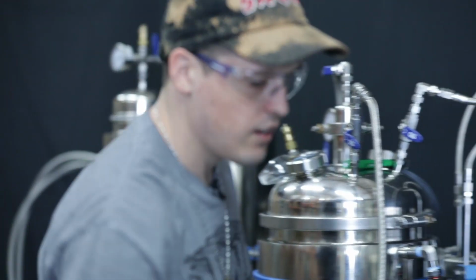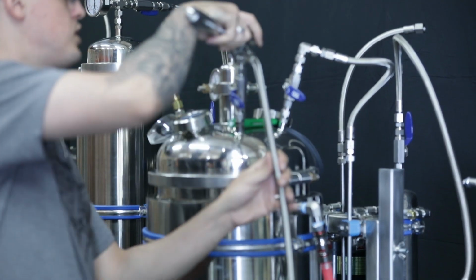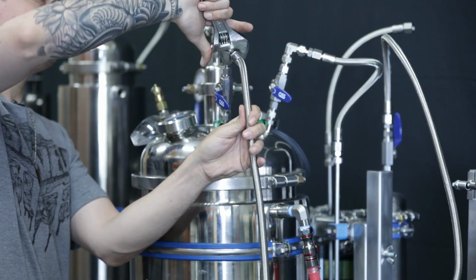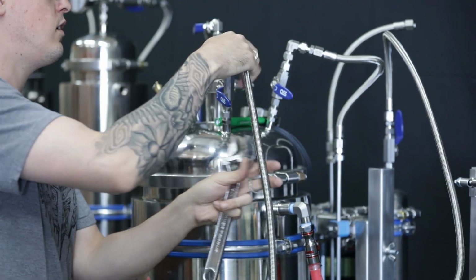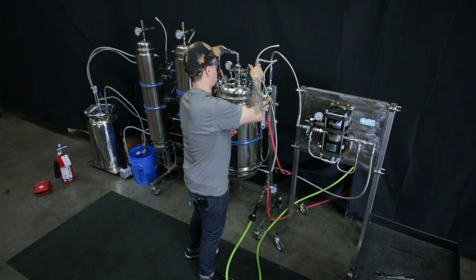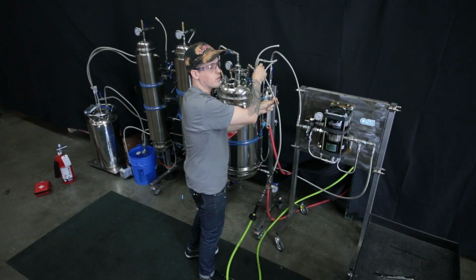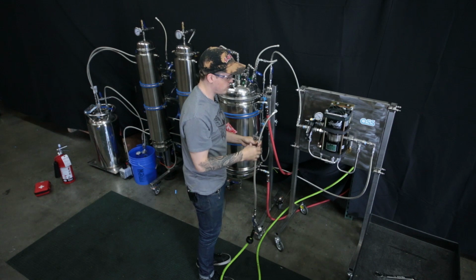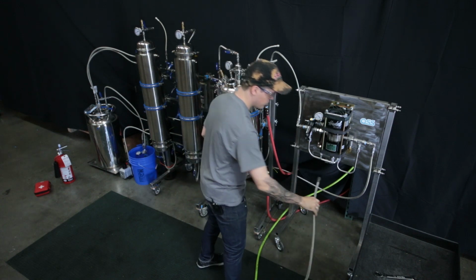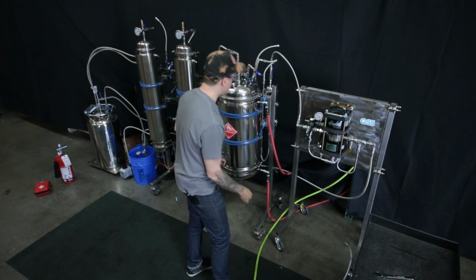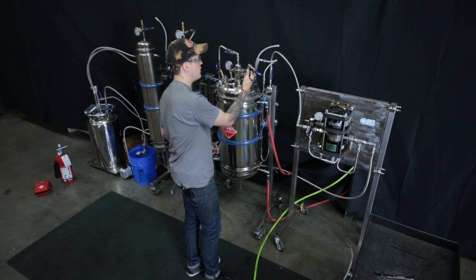All right, so now that we've done the critical pressure test, we're going to do our next safety check, and that's the vacuum check. So I'm going to go ahead and disconnect our hose here. Take my wrench. Of course, always wear safety glasses in case there's any sort of pressure blow off. You don't want that shooting in your eyes. I'm going to put my hose down for a second. I'm going to release the pressure here.